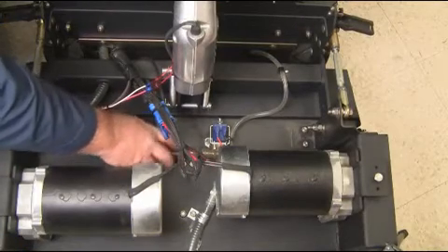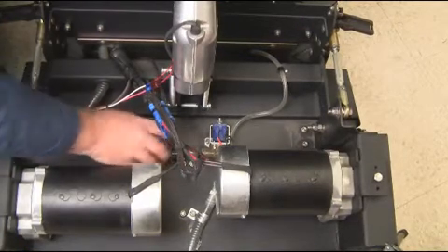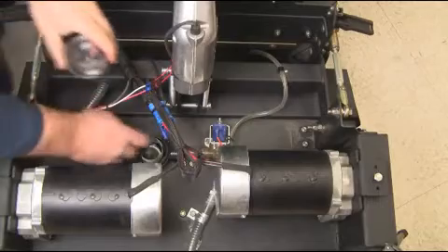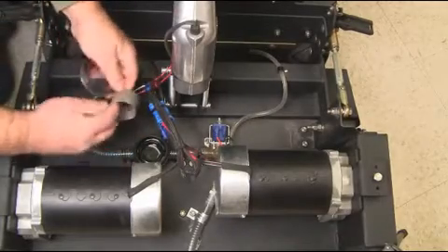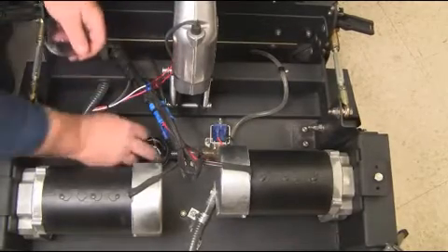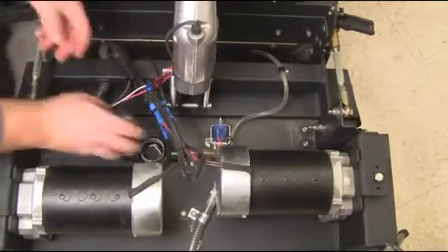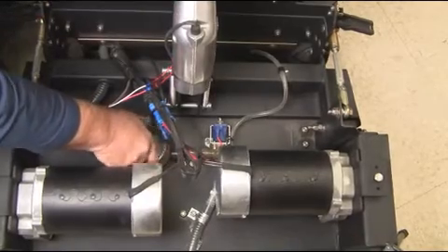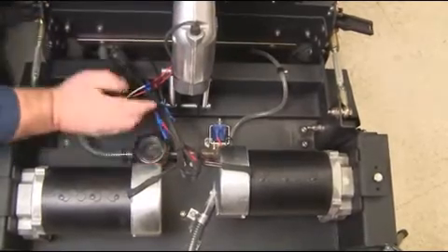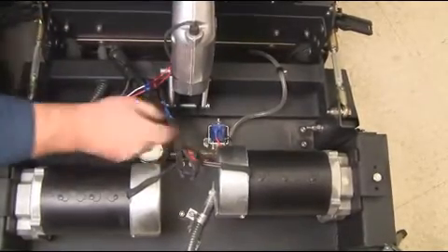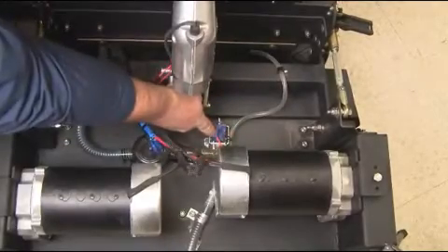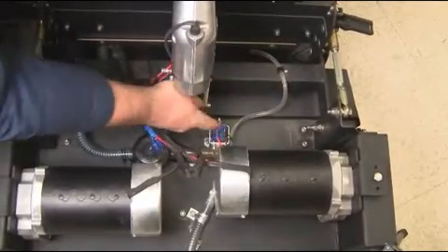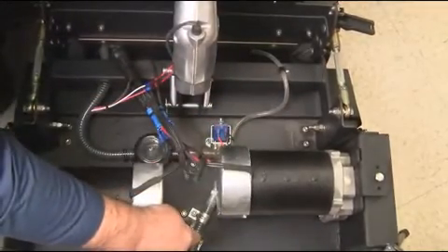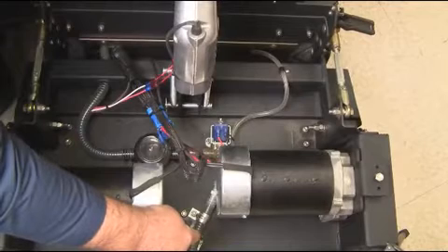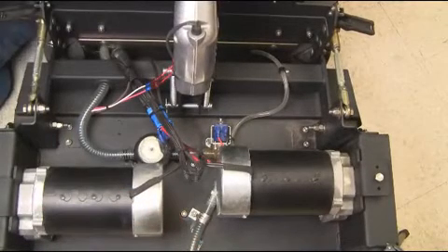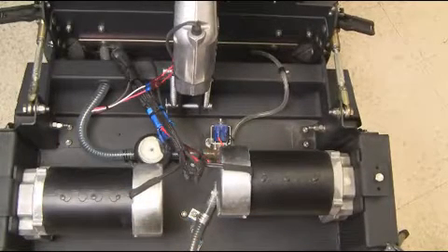At this point, check all of your wire reinforced hoses that they are in good working condition and remove the solution float screen to ensure that it is free of dirt and debris. Clean accordingly and replace. Next, check your solution solenoid valve that it is free of leaks and that the wiring is secure to the valve assembly. Check that the valve opens and closes properly when activated from the operator control panel.